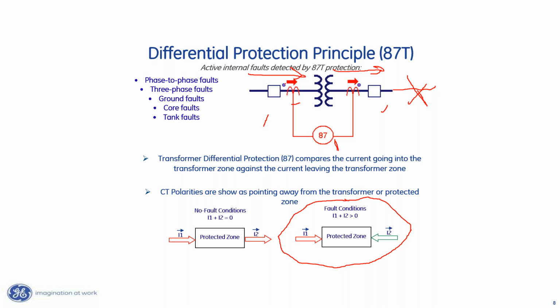But what about these CTs? If these CTs are imperfect, this might look more like 10 per unit at 0 degrees, because maybe that CT does perform perfectly, but this other CT over here performs less than perfect. So over here, instead of 10 per unit at 180 degrees, it looks like 6 per unit at 180, and 10 at 0. That vectorially sums to 4 per unit. Now that's differential current. That caused me to operate unless I do something to take care of that.